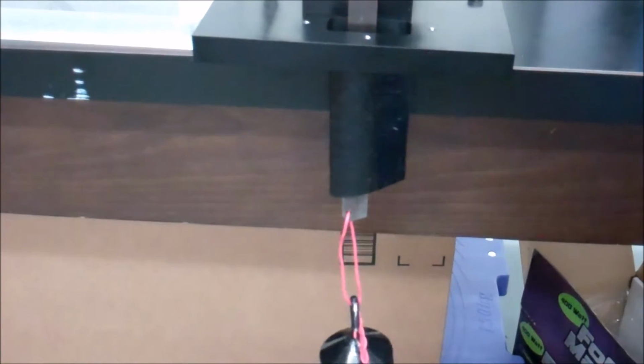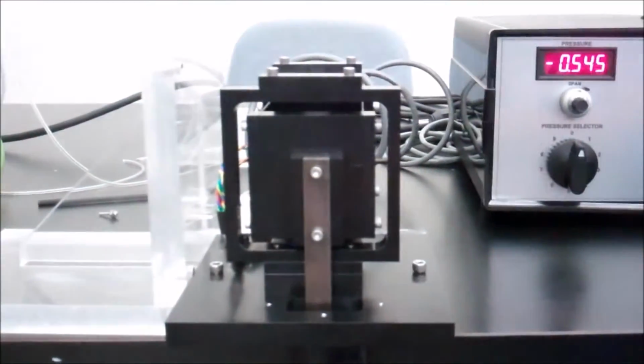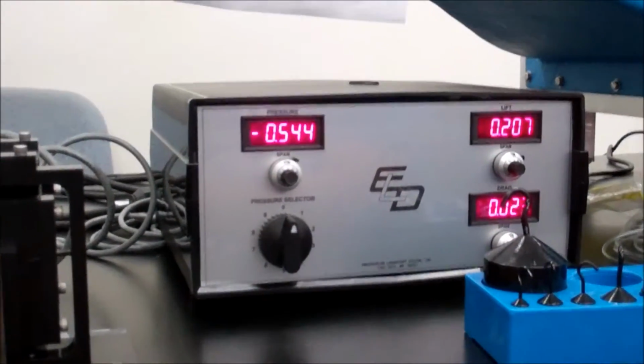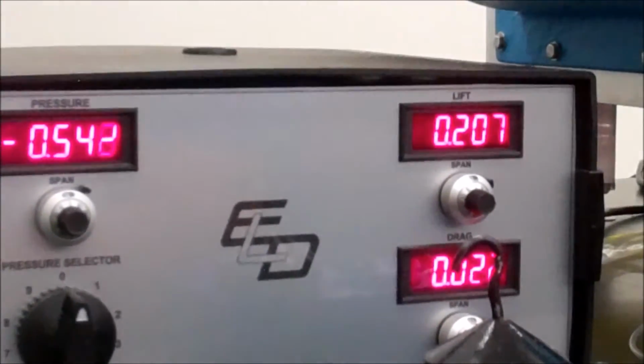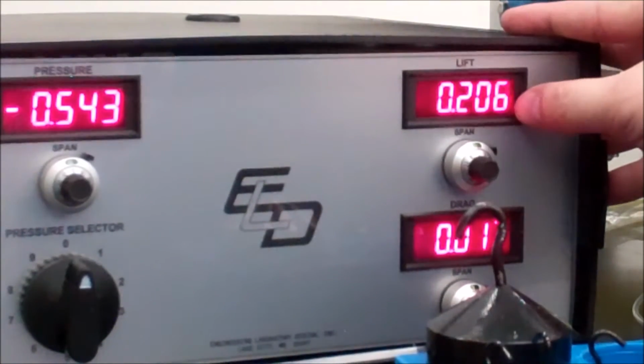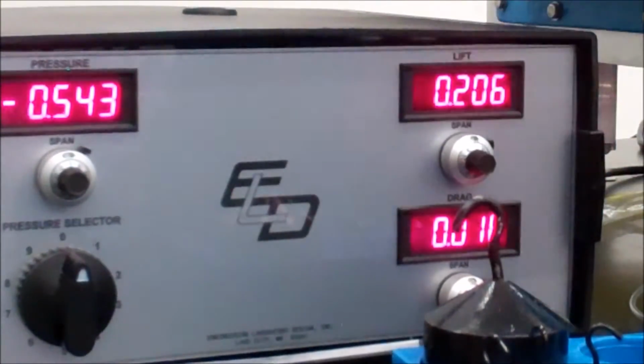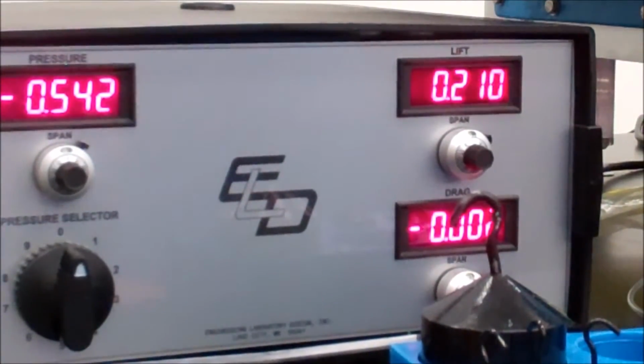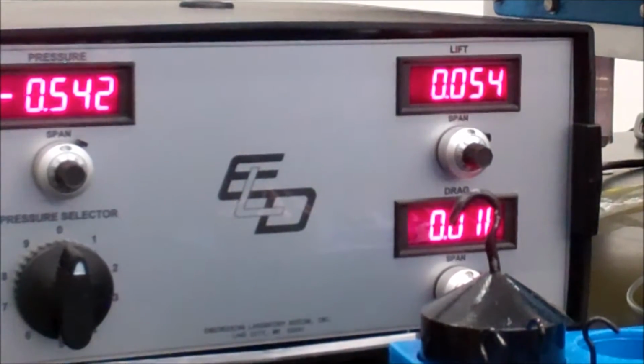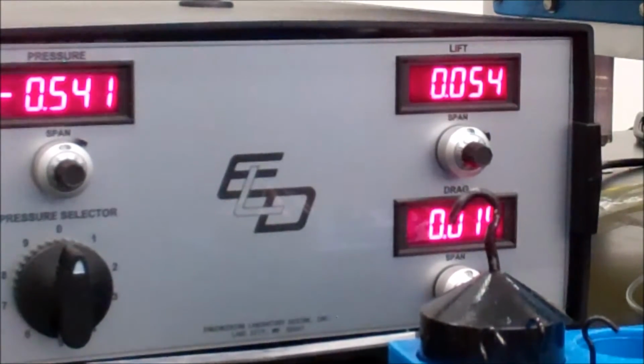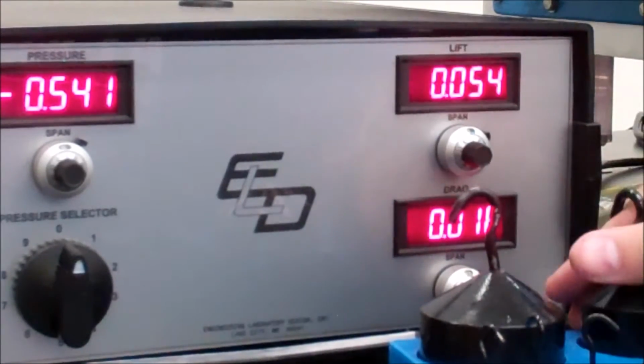Then you take a weight set, like the one that we used for the strain gauge lab, and you hang a known weight onto the unit, and because you know the weight you can calculate the force. When you apply that known weight, you look at the voltage display and make note of it. So right now it's at 0.207 with a 500 gram weight. If I take that weight off, you notice that it goes down to 0.054.